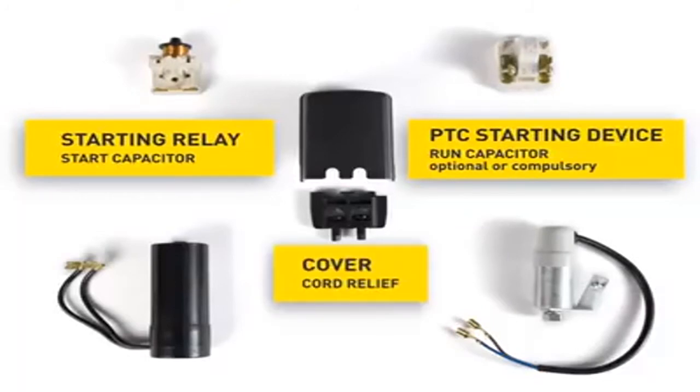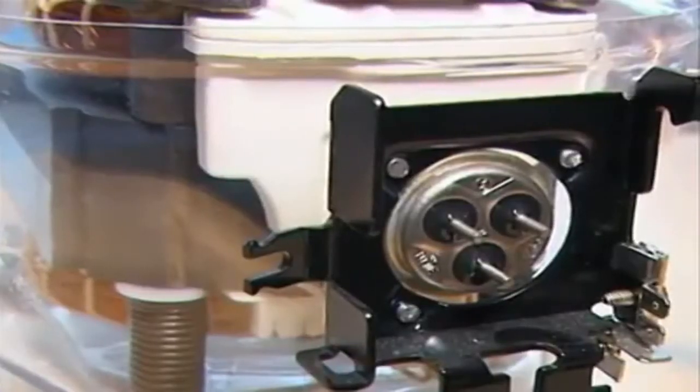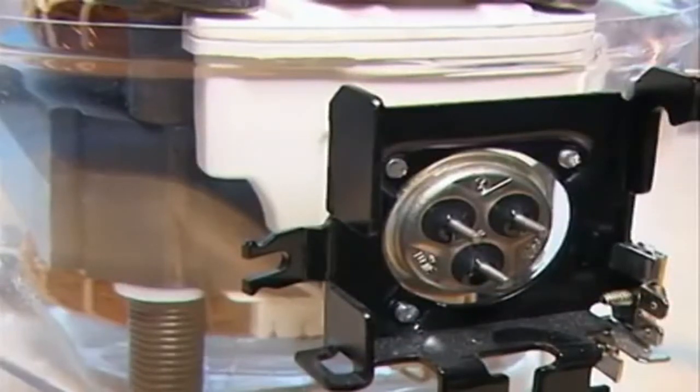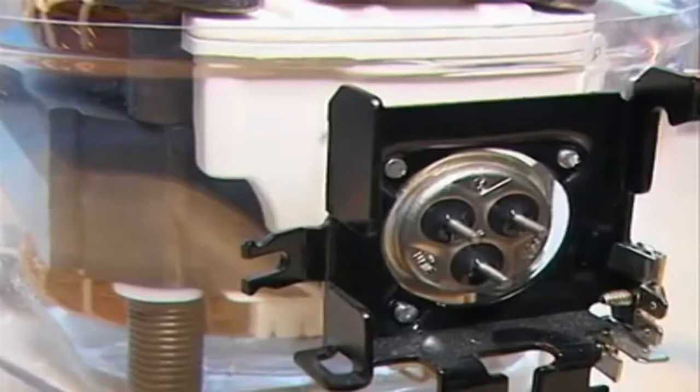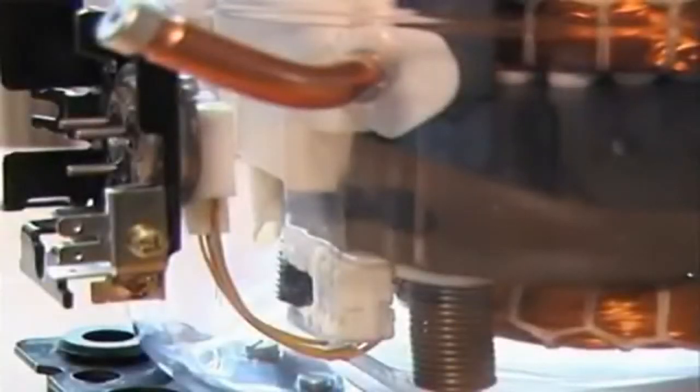The starting unit is mounted on the current lead-in of the compressor shell. It's the starting unit's task to supply the start winding with power for a short moment in order to enable the starting of the compressor. As soon as this has happened, the motor operates only through the main winding. The starting unit is connected with the current lead-in of the compressor shell. The power cable ensures a flexible connection to the motor.